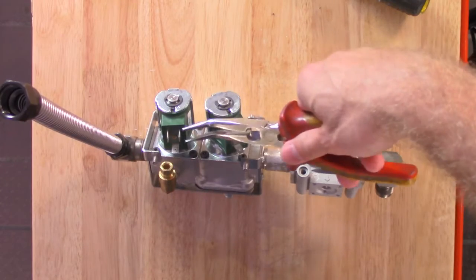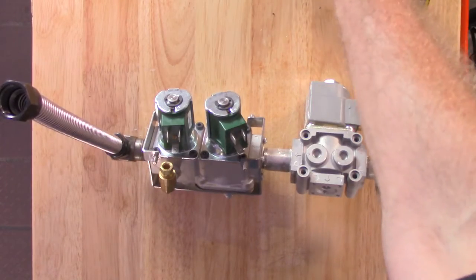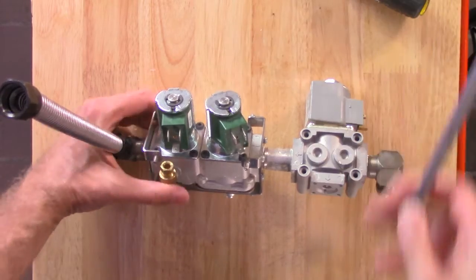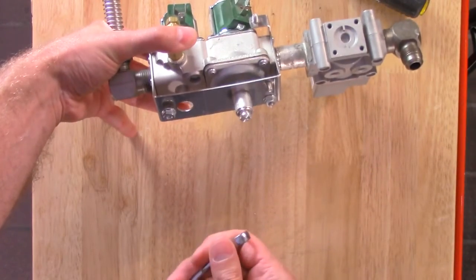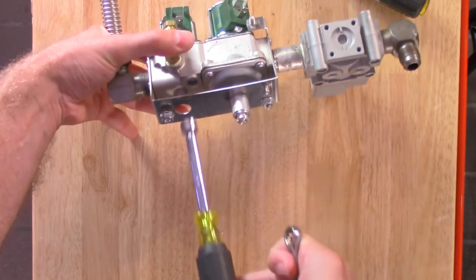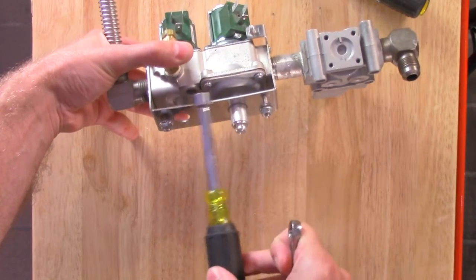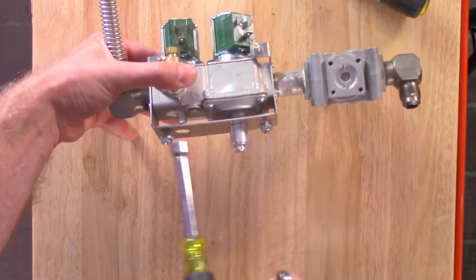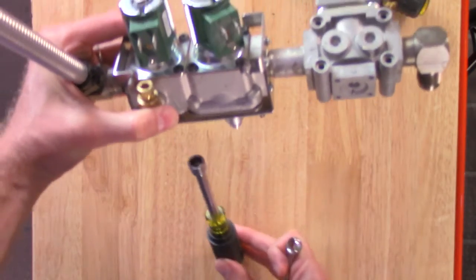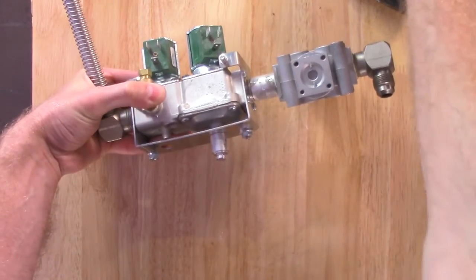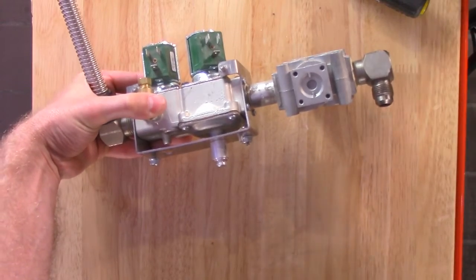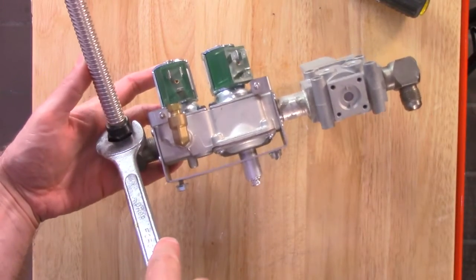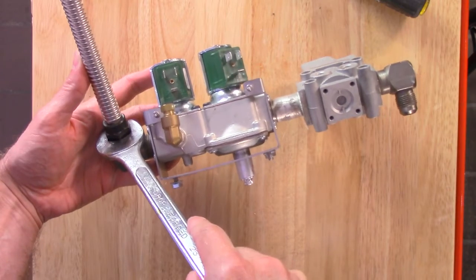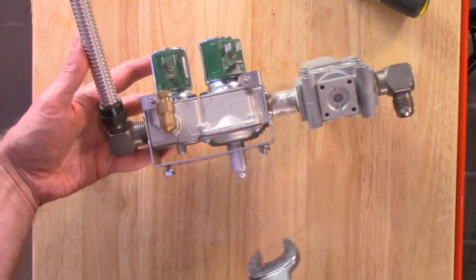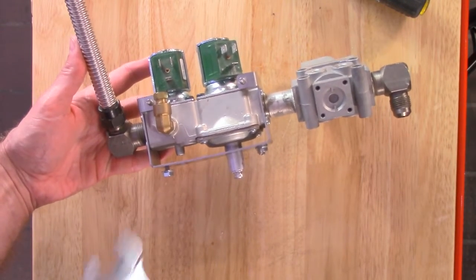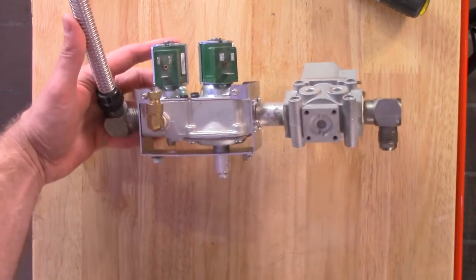Remember I said you could use these to pull the wires off if you need to, because they're tight. Then you have your 3/8 wrench or a ratchet or your nut driver. That's to get to the 3/8 nuts that hold this whole gas valve to the shroud on the fryer. This would be underneath where you're reaching up to get to this. So that's why you need your 3/8. And then you have your 7/8 to break the line loose here that goes out to the manifold. There again, you want to make sure that you have your gas supply shut off to the unit if you're going to have to change out the gas valve.